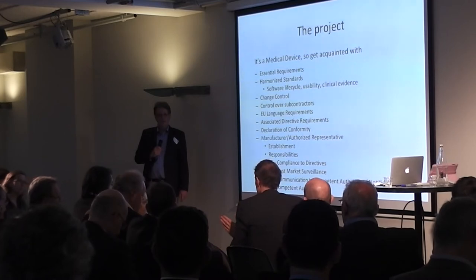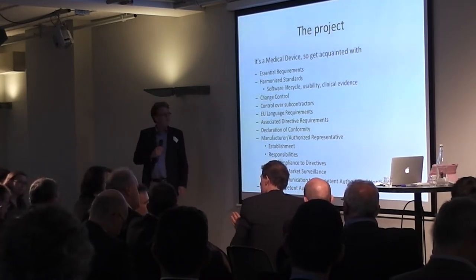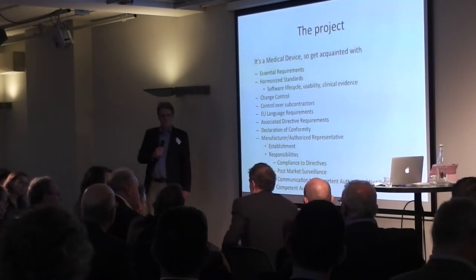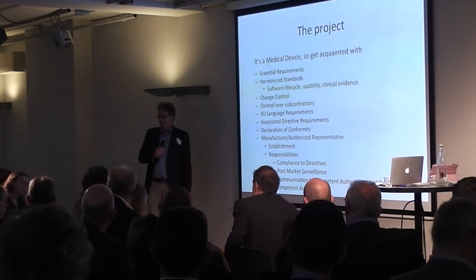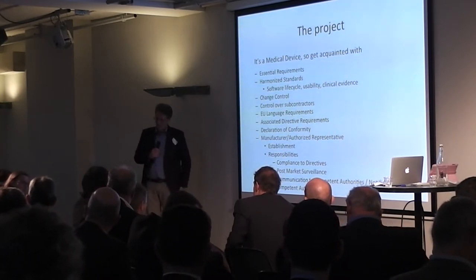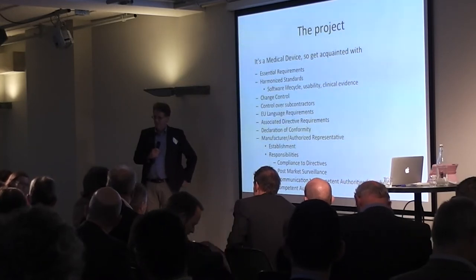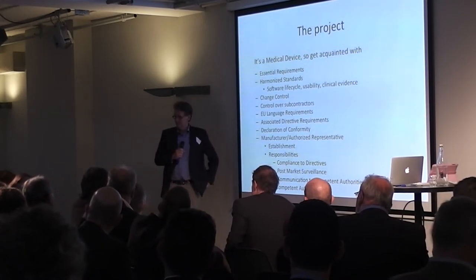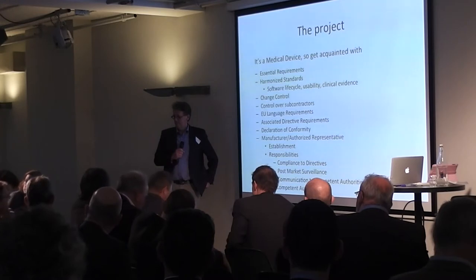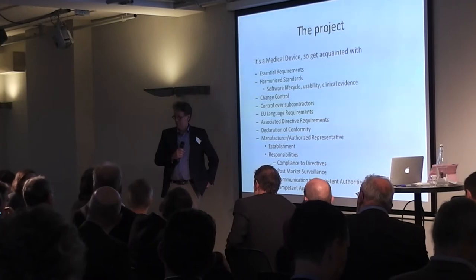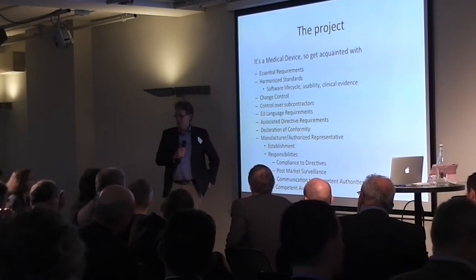But if I completely substantiate the functionality — for example, if somebody else is already doing this with software that does it exactly the same way — then you can say I don't need to do the clinical trial. But saying that software does something exactly the same is where you enter a challenge. If you only get an analysis of data, as has been done over many tens of years, equivalence is the buzzword. You need to justify the technological equivalence — that you can use the available literature to support the way you implement it.